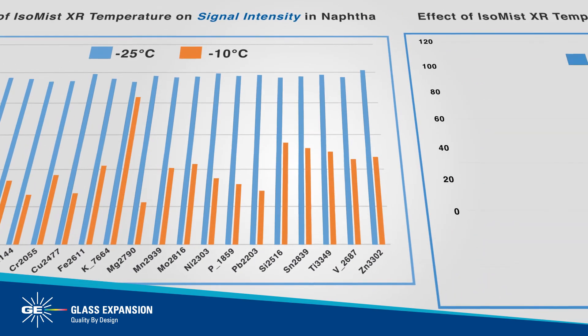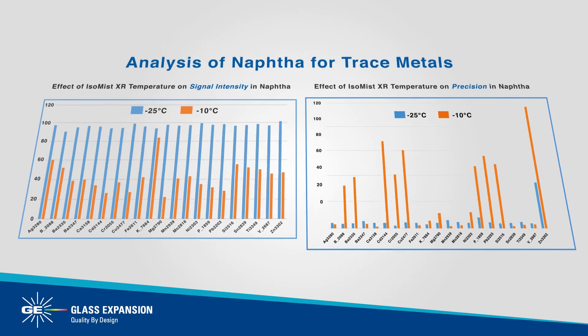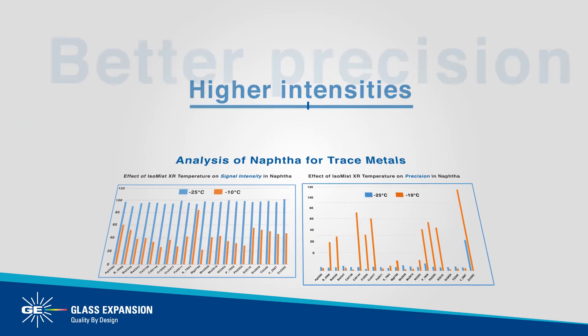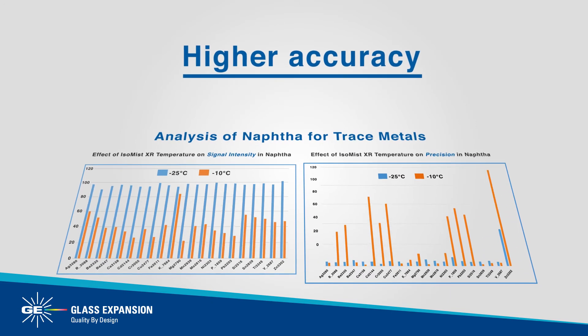The extended temperature range makes the IsoMist XR the perfect tool for analyzing volatile solvents. With the ability to maintain a temperature of minus 25 degrees Celsius, the IsoMist XR allows for the direct analysis of naphtha without dilution, resulting in higher intensities, better precision, and higher accuracy compared to previous work at minus 10 degrees Celsius.